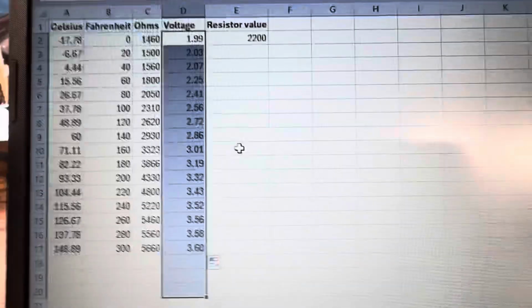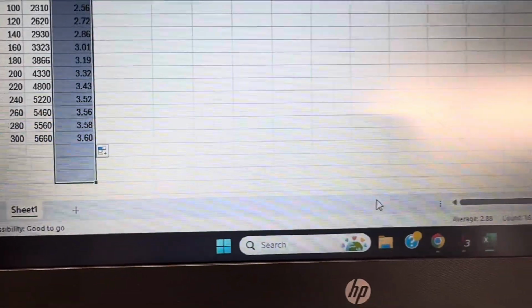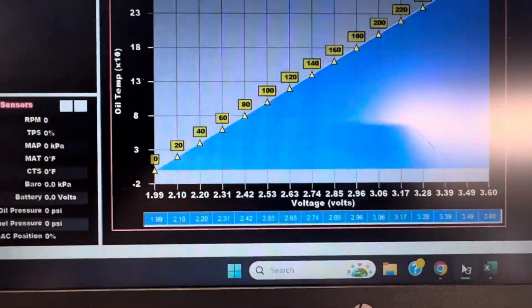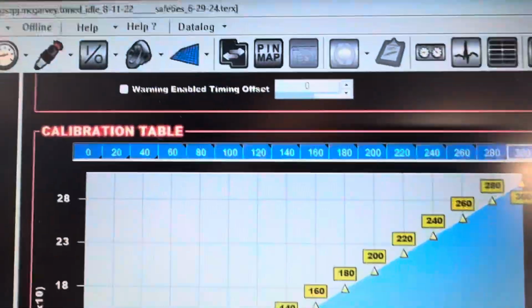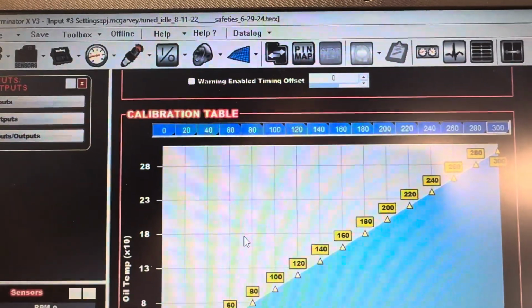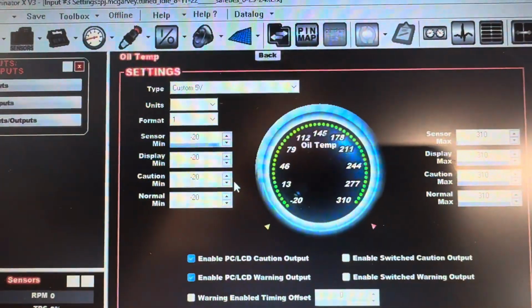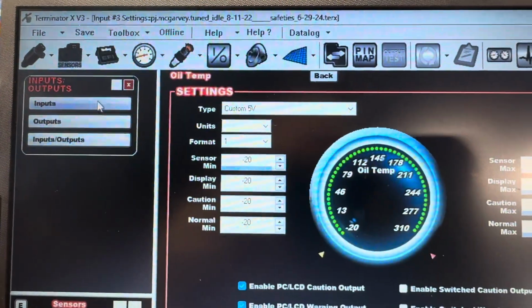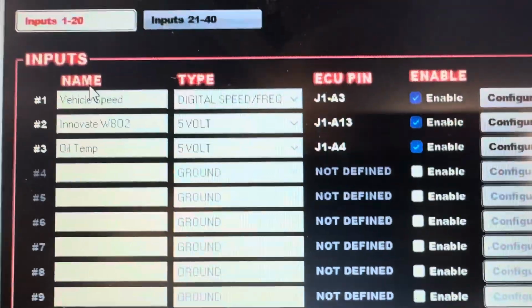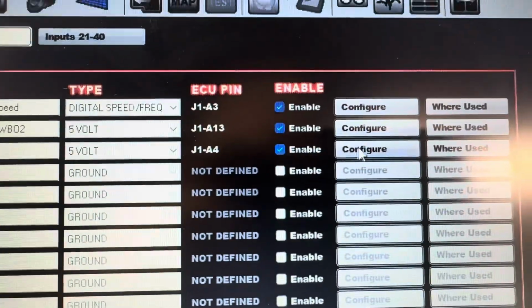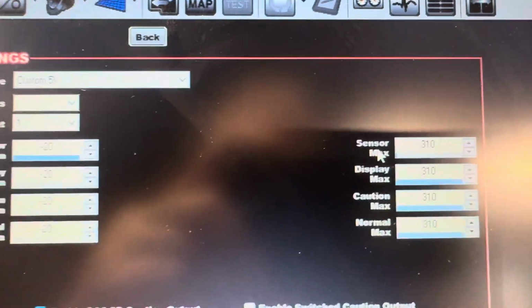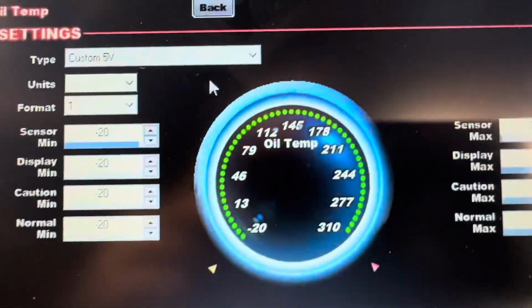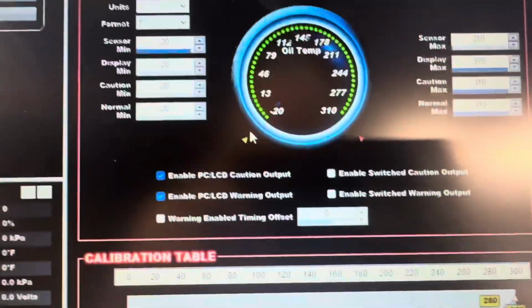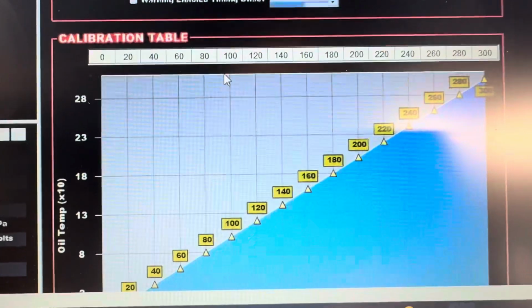So then you go into Terminator X, to your oil temperature sensor. You go into inputs, you've got oil temp, go to configure. You can set all this stuff up how you like, but down here is the calibration table.